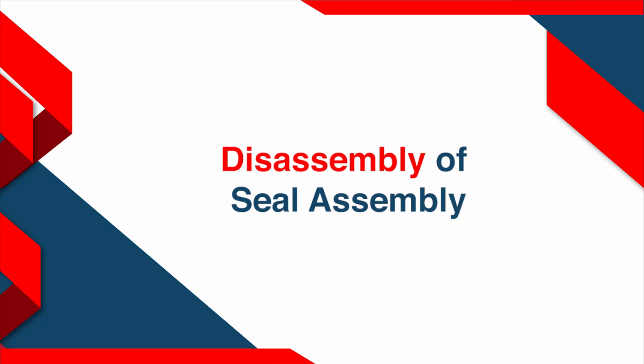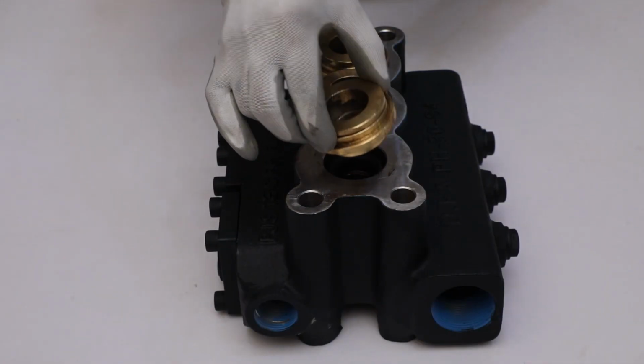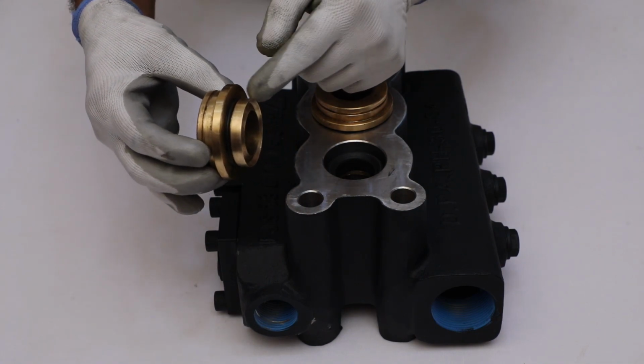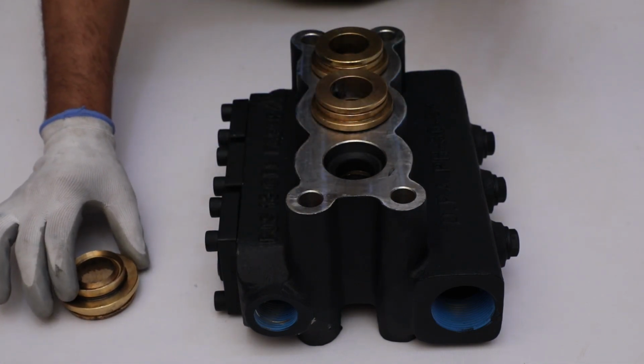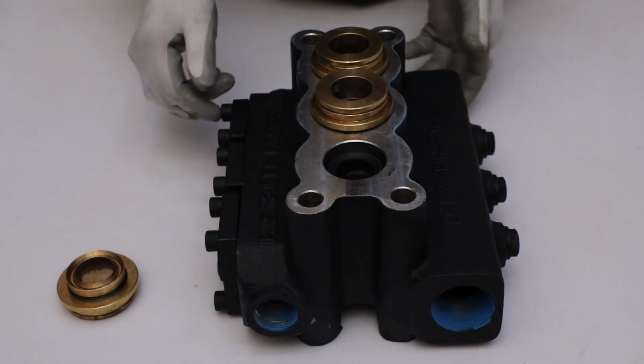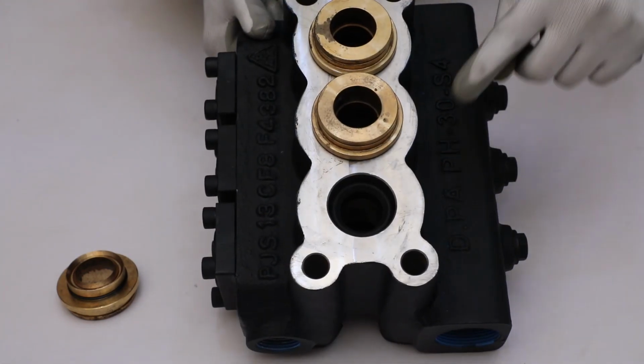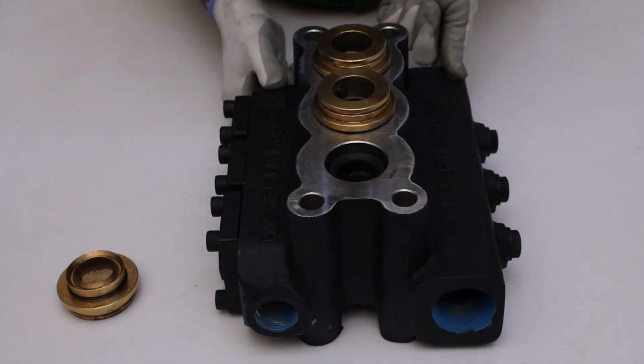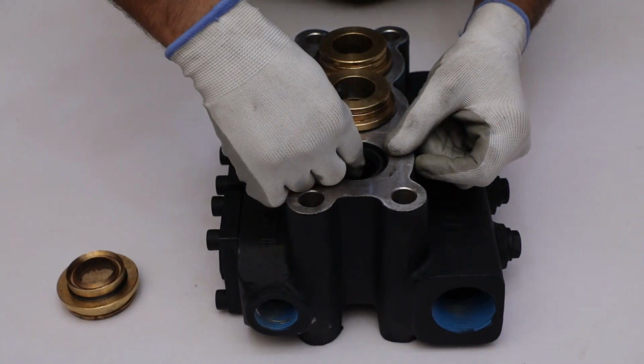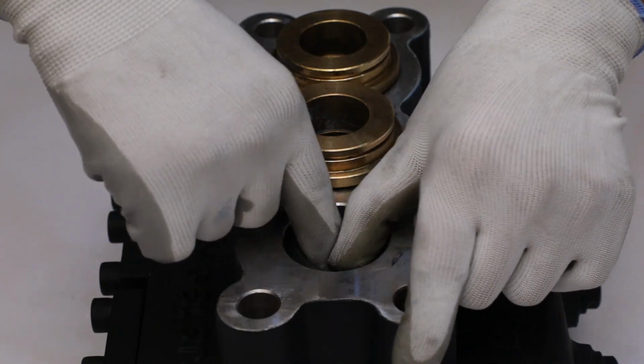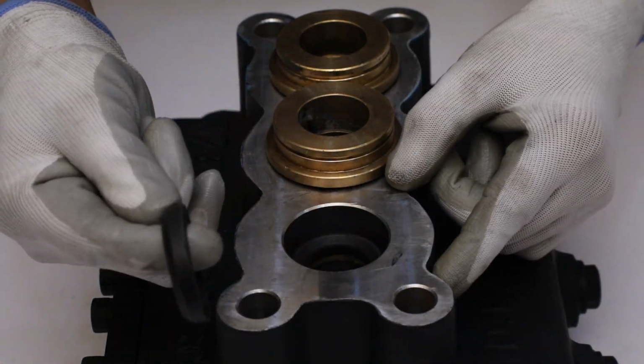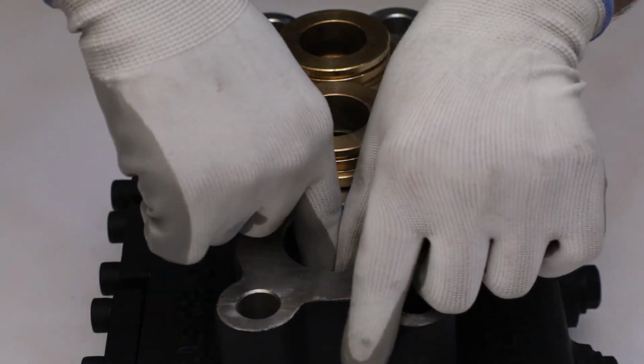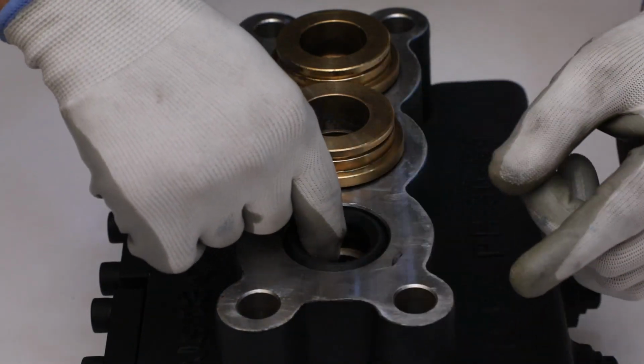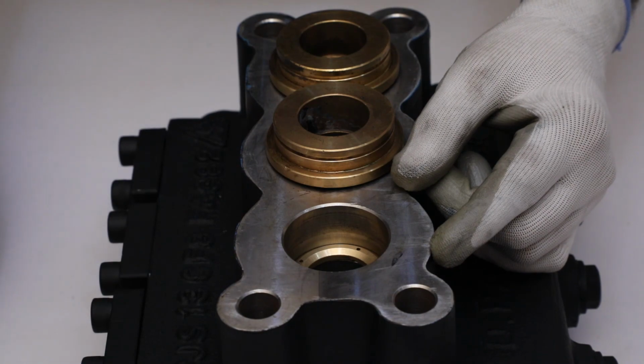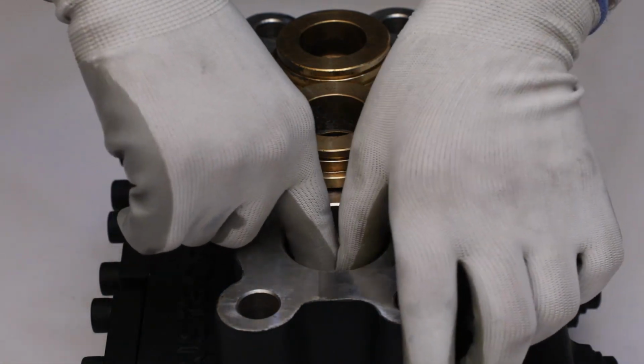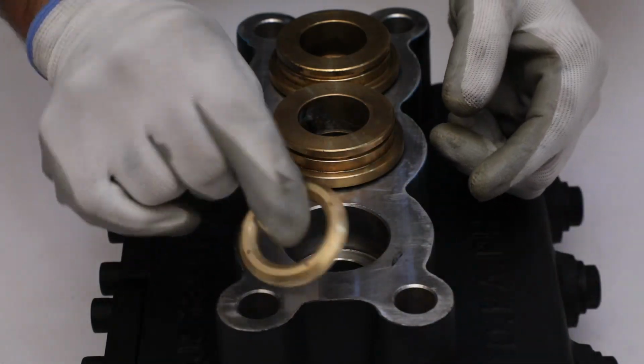Disassembly of seal assembly. Take the packing support from the pump head. This is a chevron type plunger seal. Take out it from the pump head manually. Then, take out chevron type plunger seal from the pump head. At last, pull out the packing ring manually from the pump head.